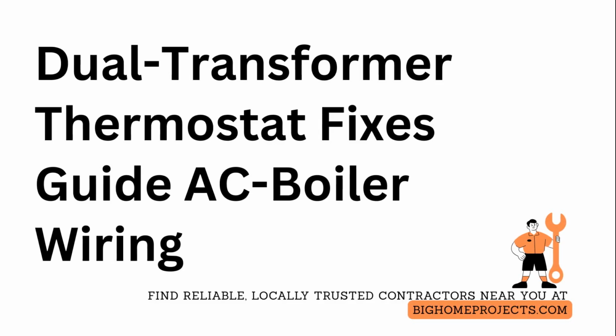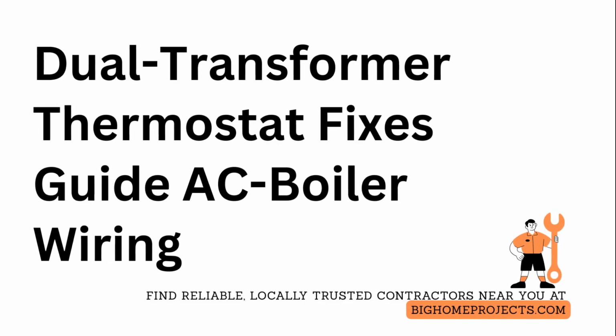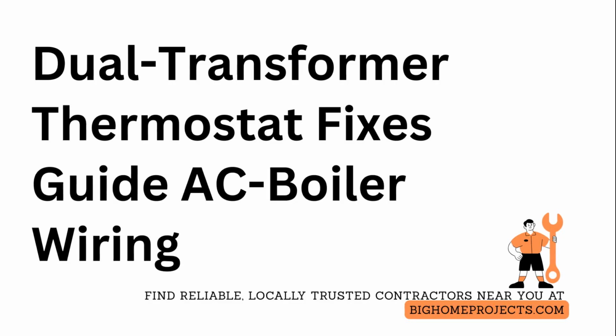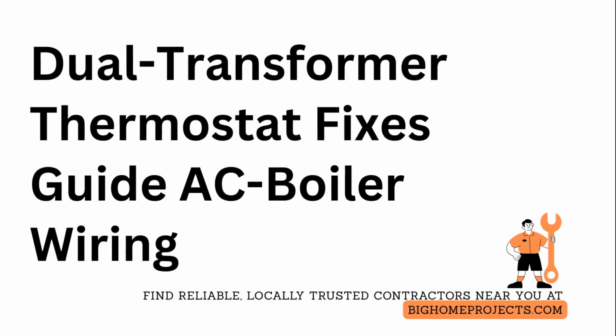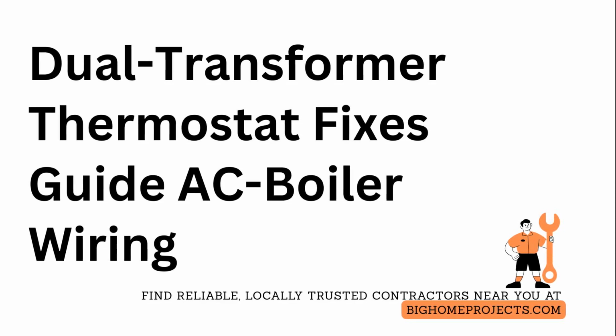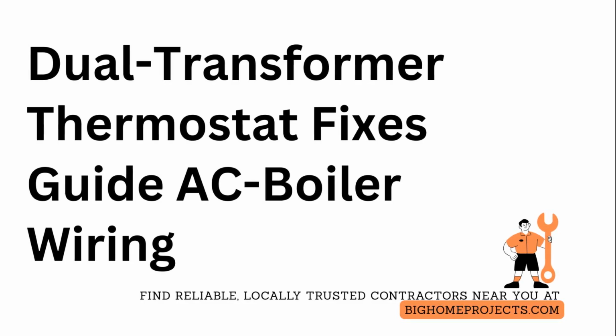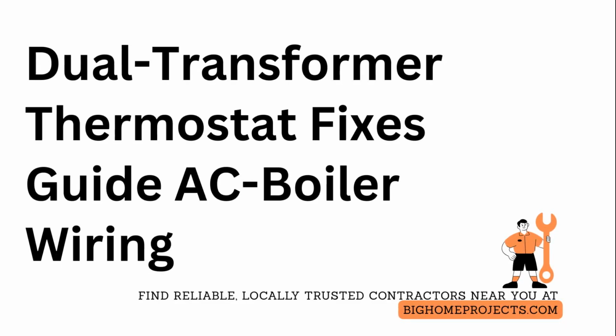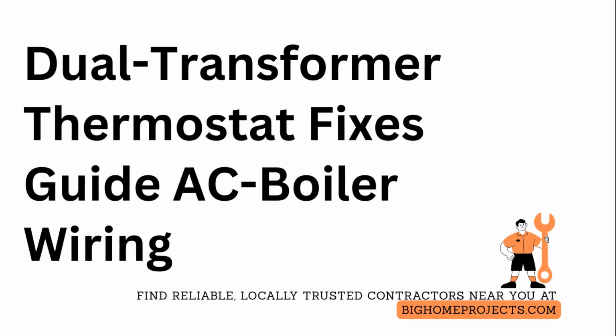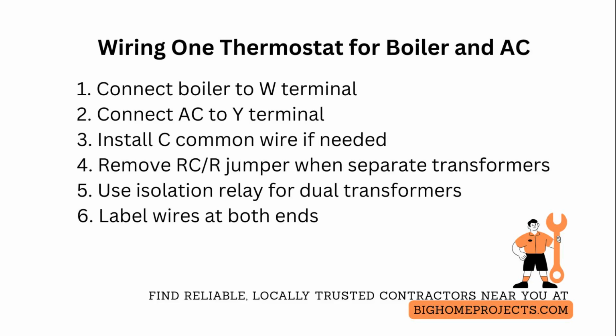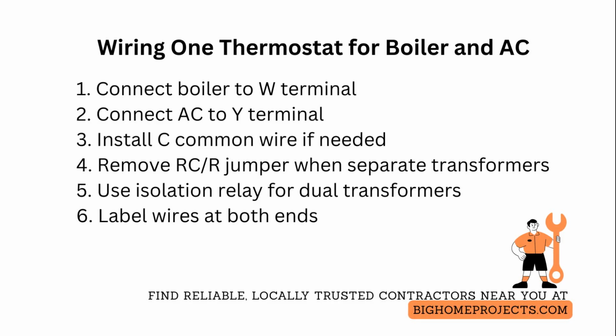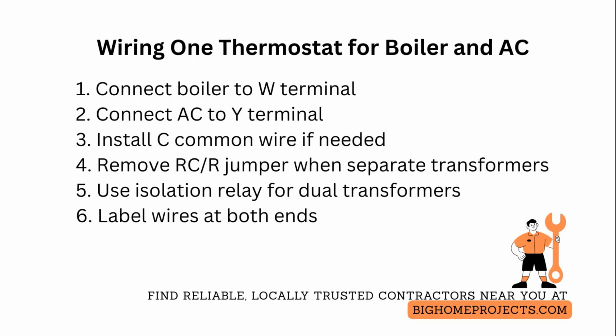Manage both a boiler and an air conditioner with one thermostat by wiring each system to its correct terminals and ensuring the thermostat supplies separate control power lines without a redundant RC/R jumper tying the two systems together. Set the thermostat to control heat call and cool call independently. Connect the boiler's thermostat lead to the W terminal and the air conditioner compressor contactor lead to the Y terminal. Then run a dedicated common wire back to the thermostat C terminal.